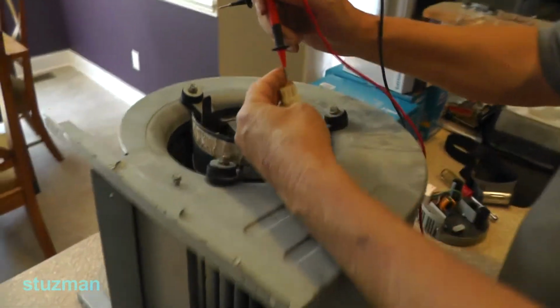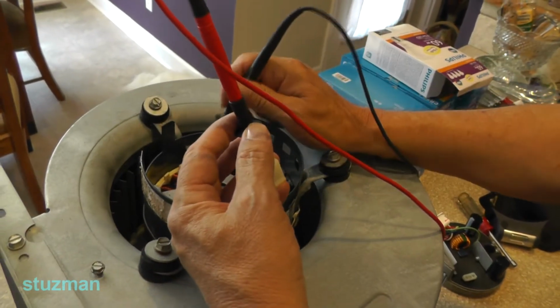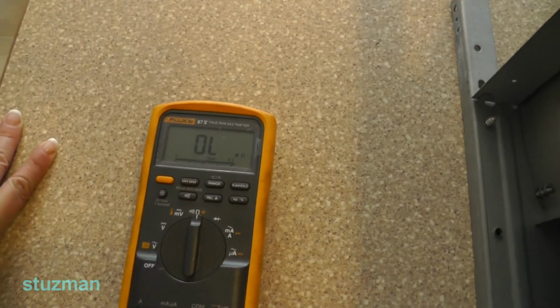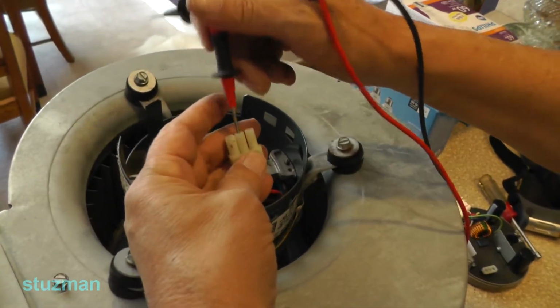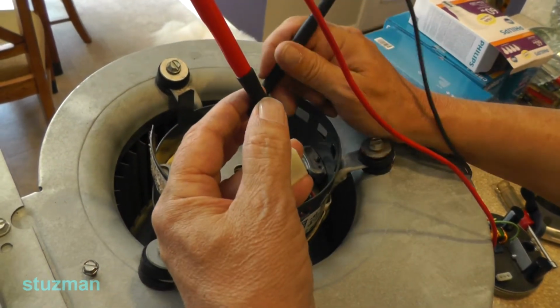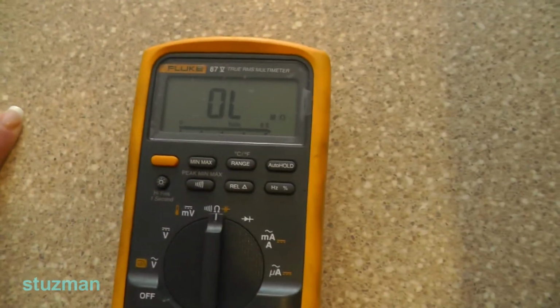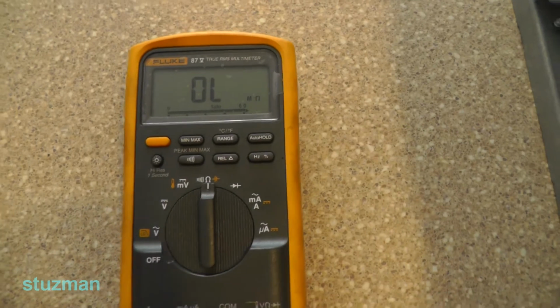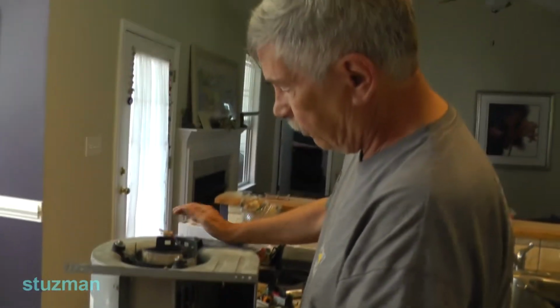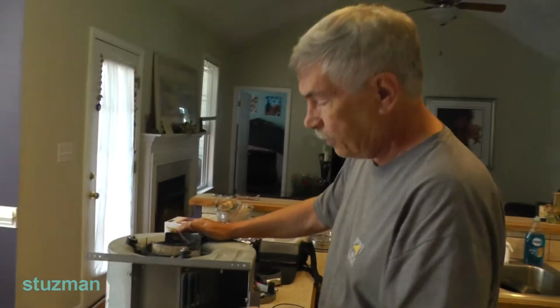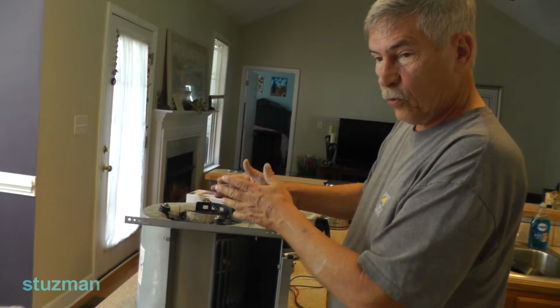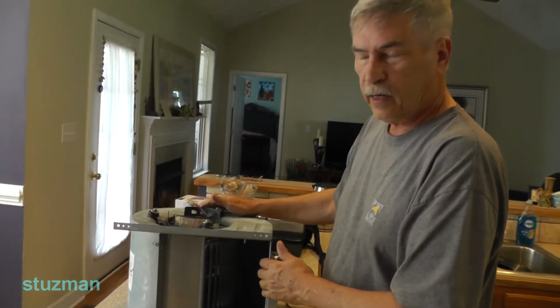So then, move it over to your next winding, do the same thing, okay? Again, that's good. Again, move it over to your last winding, go to ground, and you see that one's good. All right, now obviously, motors do go bad, you know. You could have stator windings that can short out. You can open. If you see anything that's open or shorted from what we just showed, the motor's bad.